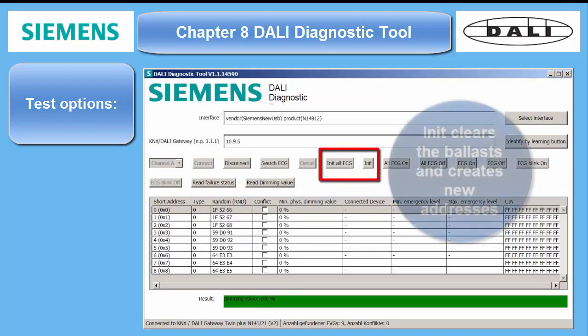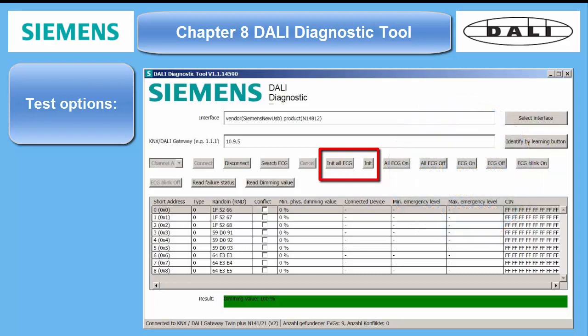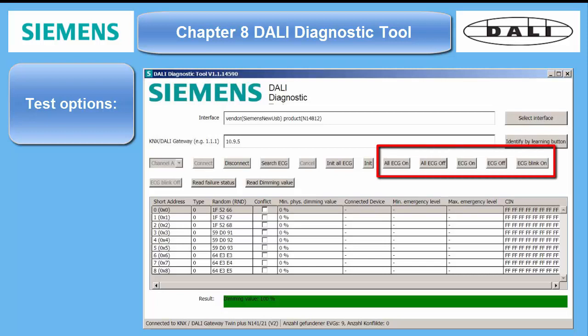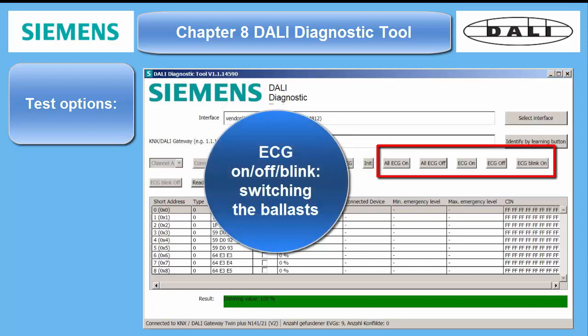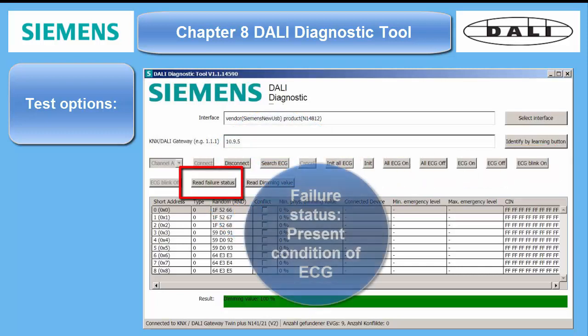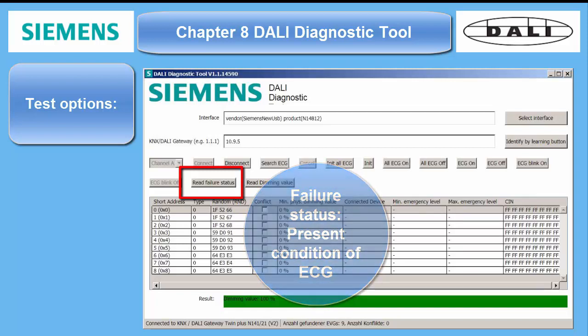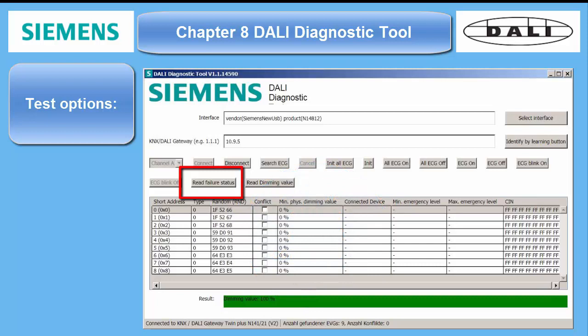Test options: 'Init' initializes all ECGs, clears the ballast's memory, and assigns randomized new addresses. This is used to get rid of conflicts caused by duplicate short addresses. 'ECG all on,' 'off,' and 'ECG blink' are self-explanatory. 'Read Failure Status' returns the present condition of the ECG — lamp on, off, or invalid condition. 'Read Dimming Value' is also self-explanatory.